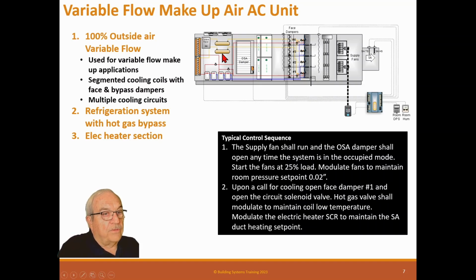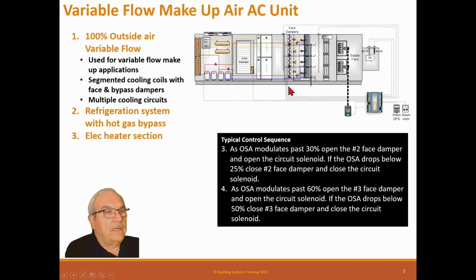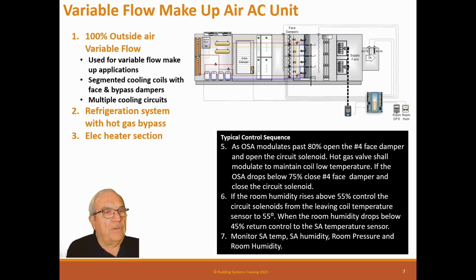Now that's the first circuit. So we got first circuit operating. Okay, as the outside air modulates past 30%, open number 2 face damper and open the circuit solenoid. If the outside air damper drops below 25%, close number 2 face damper and close the circuit solenoid. As the outside air modulates past 60%, open the supply air number 3 face damper and open the circuit solenoid. If the outside air drops below 50%, close number 3 face damper and close the circuit solenoid. As the outside air modulates past 80%, open the number 4 face damper and open the circuit solenoid. Hot gas valve shall modulate to maintain coil low temperature. If the outside air drops below 75%, close number 4 face damper and close the circuit solenoid.